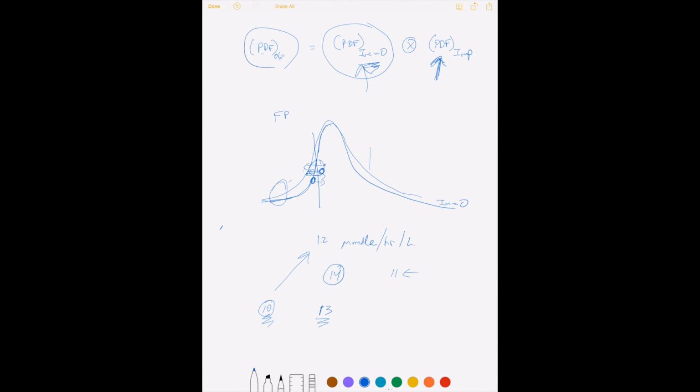So this leads to a very important theorem that comes out of this paper, and you can read it, that the most important assay parameter in comparing two different assay platforms, let's say fluorescence to mass spec, in determining who's going to have the higher false positives, is not the absolute activities. So if fluorescence gives higher activities because they're in an optimal buffer compared to mass spec, that's not important. It's the imprecision at the cutoff.